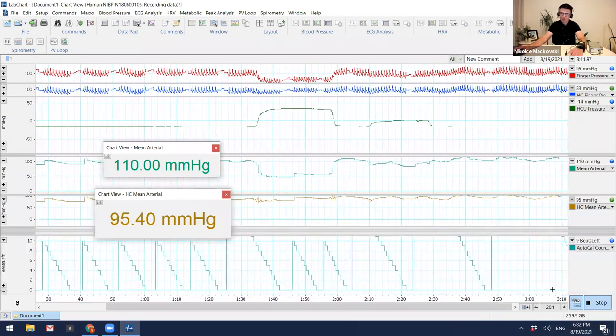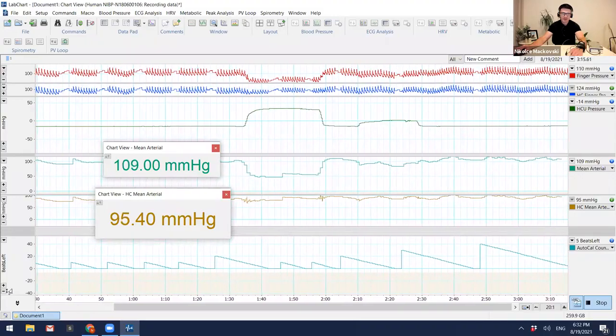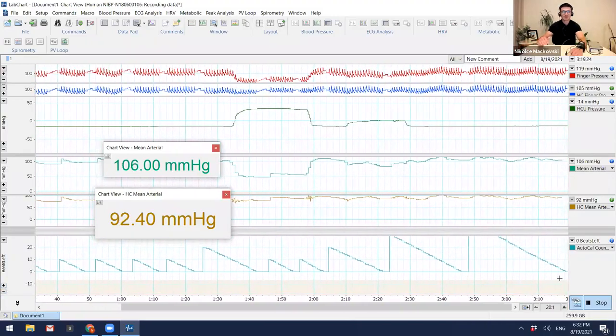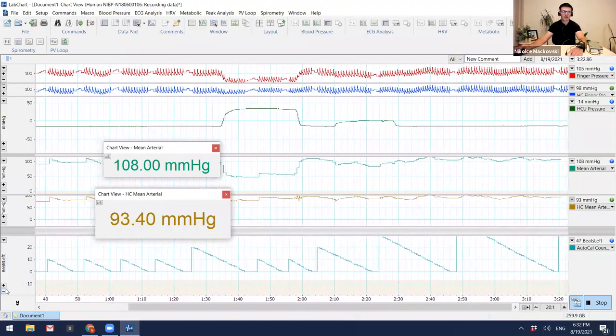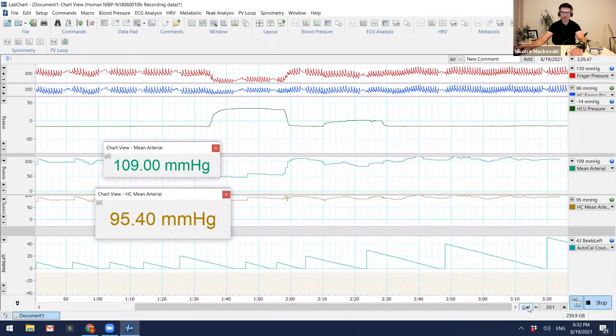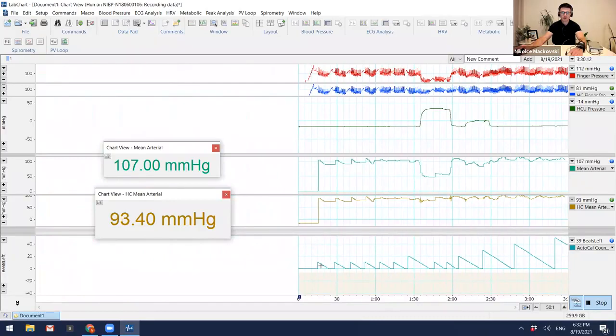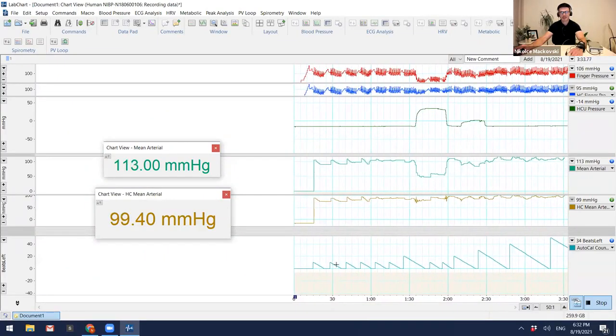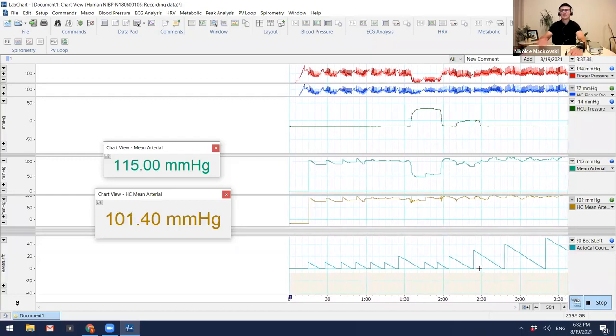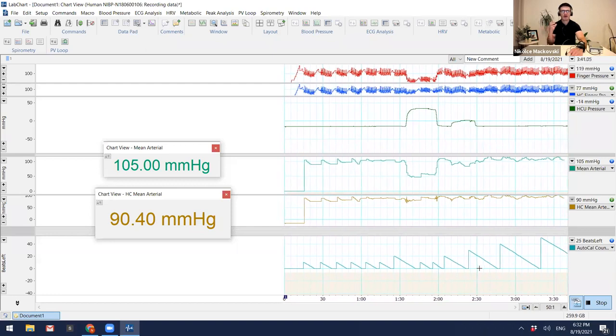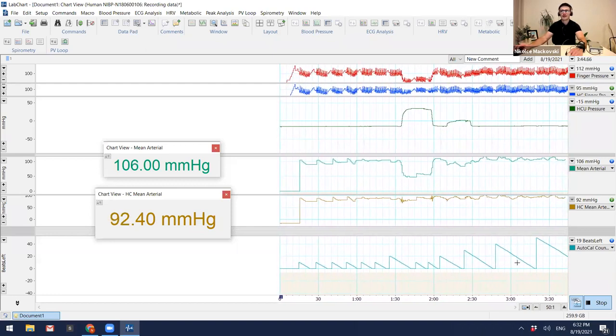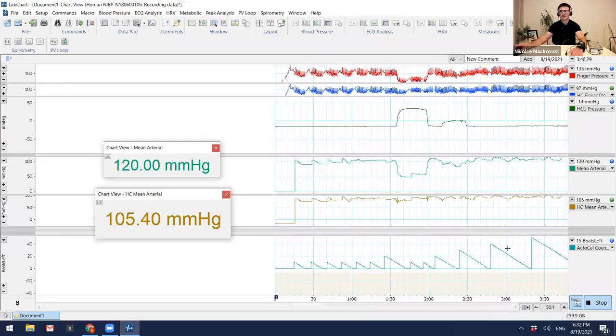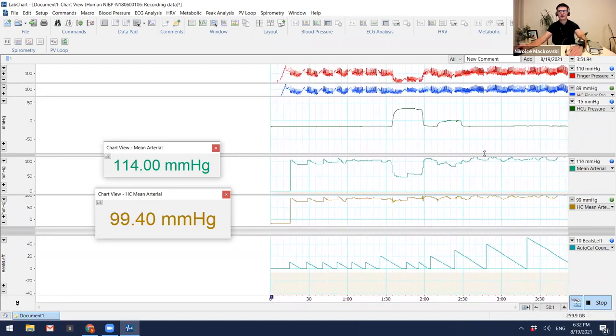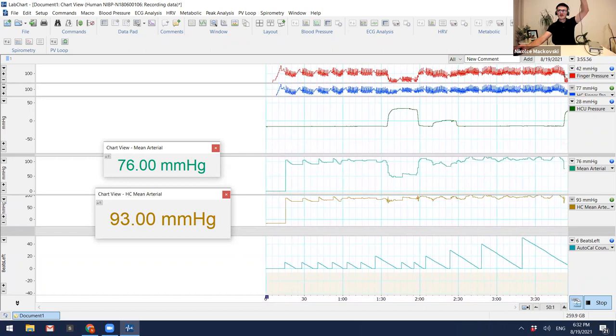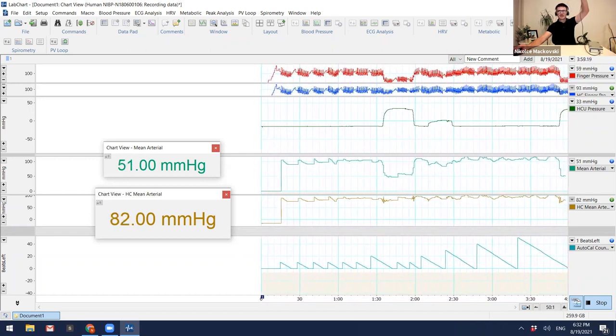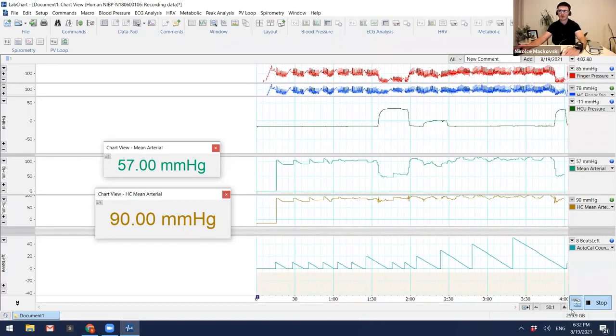So now it doesn't require all those constant autocals. Other channels here you can see. The bottom one here, if I zoom out a little, these are the steps. So this is the autocal step. When it reaches the bottom of the steps, that's when it autocals, and then of course it goes back up. Notice that the autocals were short. Remember the top means how many steps, so it took 10 beats to get to autocal, 10 beats to get to autocal. But as the set point has been found, the correct unloaded diameter, the cuff pressure equals the pressure within the artery, so it does not need constant autocal refreshes. That's why it's longer. And once again, if I move my hand above, you can see that the finger pressure crashes, but the HCU pressure stays the same. So pretty handy to use.